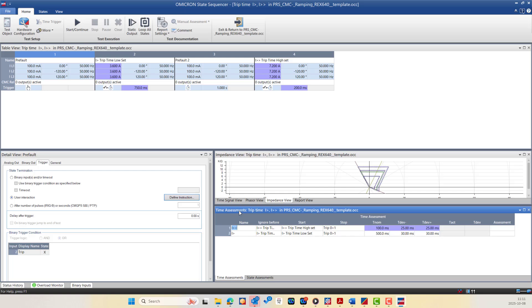In the Time Assessment view, the State Sequencer allows you to measure and automatically evaluate the time intervals between different states or trigger events — for example, to determine the trip time of the protection relay. This view provides a clear overview of all measured times, helping you verify that the relay performance matches the expected operation criteria. Results can also be automatically assessed against predefined limits and included directly in the test report for efficient and accurate documentation.